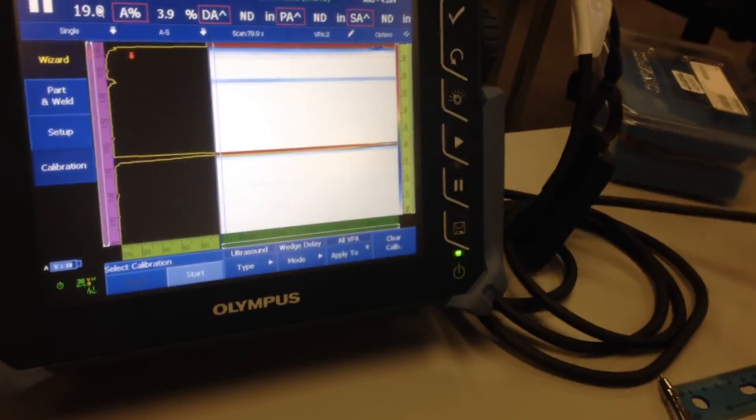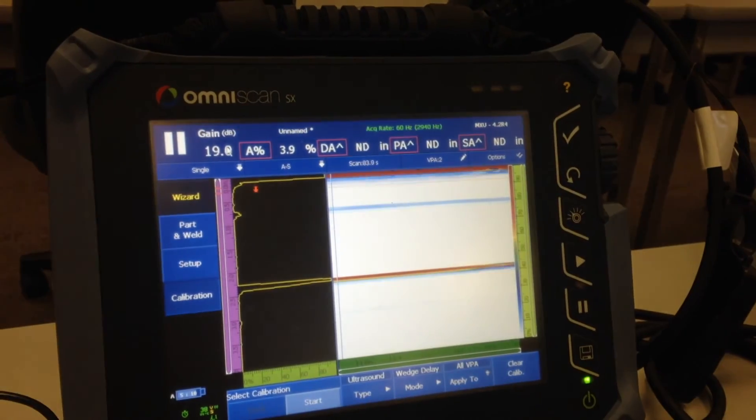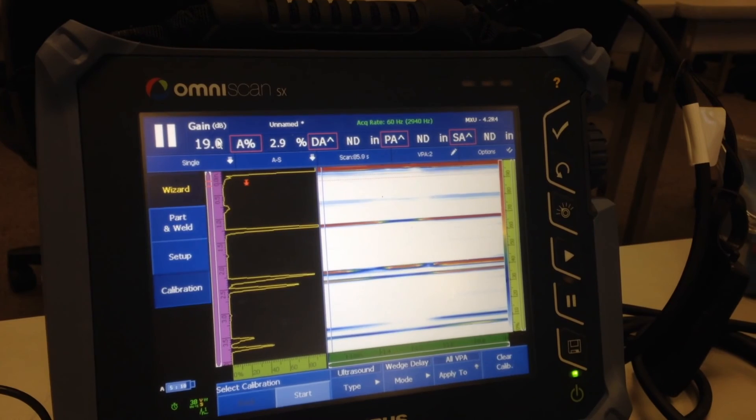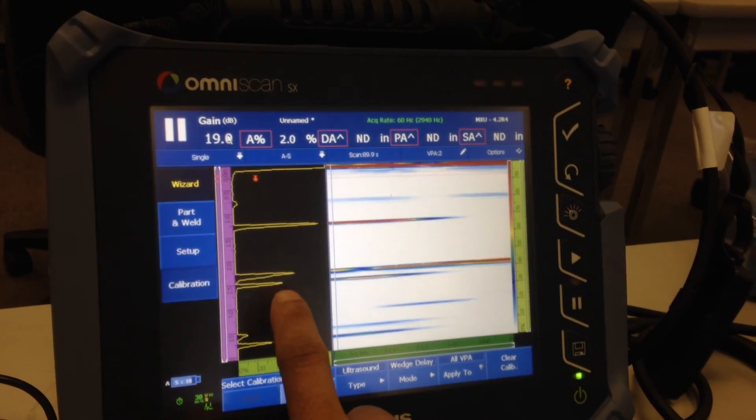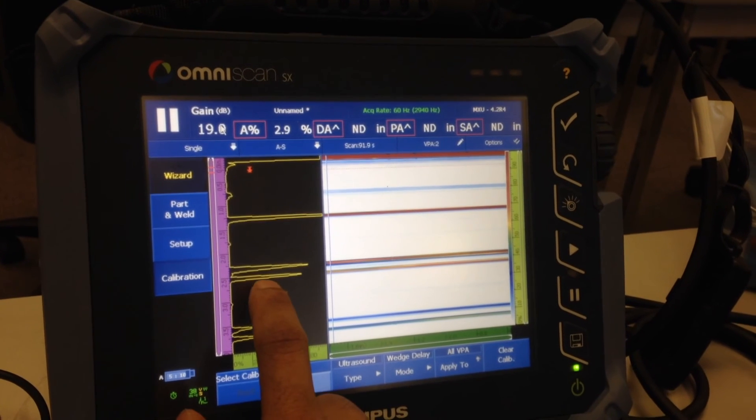Now once you find out the wedge signal, then place your probe and wedge on the calibration block and watch for the other signals that pop up on the screen, and that is your actual back wall.